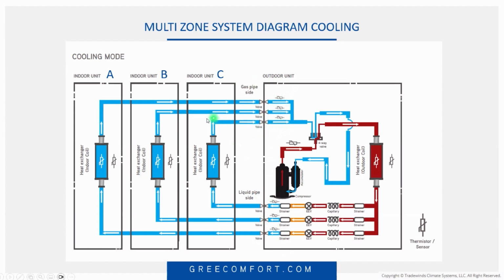Because the thing hasn't been running for 30 minutes, all those temperature sensors are reading the same outdoor temperature because they're sitting there stagnant. Right? Same with the liquid. Run down those. If I got 20, 20, and all of a sudden 5, I've just found the bad thermistor. So I know I need to change that thermistor on that circuit or change all of them. I don't really care. But you know you've got one bad one, and that's why that circuit's not working.